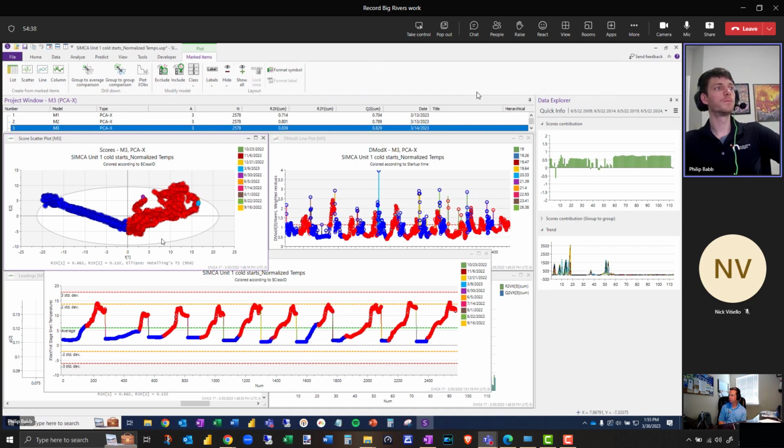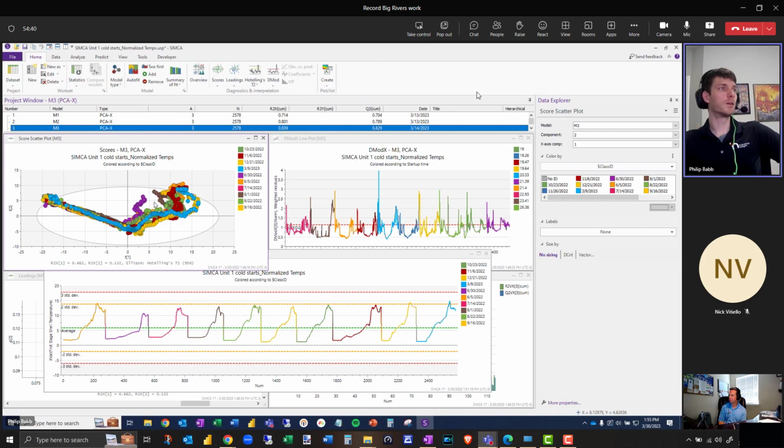And so why is this data so spread out, right? That's the next question we're going to ask. This looks great over here, but then they open their steam valve and they start heating the turbine and everything separates. So that becomes the focus of the analysis, right? Maybe there's something operationally happening in here that they could hone in on and try to tighten up, right?